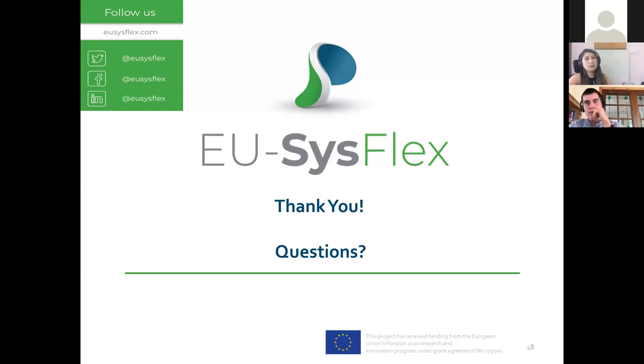Finally, would be load models. We use a load model that looks a lot like a load model you'd have seen in the 80s. And if you think how different a household is and demand types are across that time range, there needs to be some real work in updating our demand models, both in dynamics, the distribution of demand, and how we update those over time. You know, the time of day and the date changes, to make sure that we're getting demand right, because it's half the system dynamics, really. There's a big focus on generation, but you've got to get demand right, especially with the emergence of demand side management. If we want flexible demand, we've got to model it right.